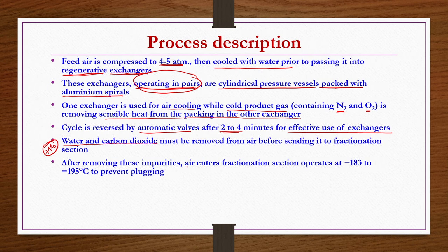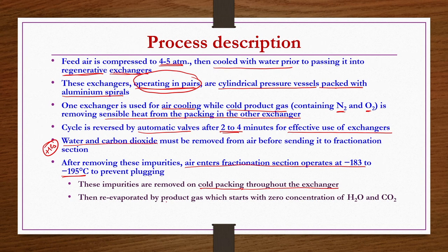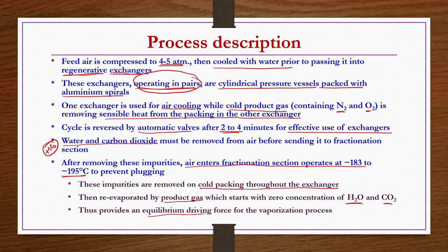After removing these impurities, air enters the fractionation section operating at minus 183 to minus 195 degrees centigrade to prevent plugging. These impurities are removed on cold packing throughout the exchanger, then re-evaporated by product gases N2 and O2 which start with zero concentration of H2O and CO2. This provides an equilibrium driving force for the vaporization process.